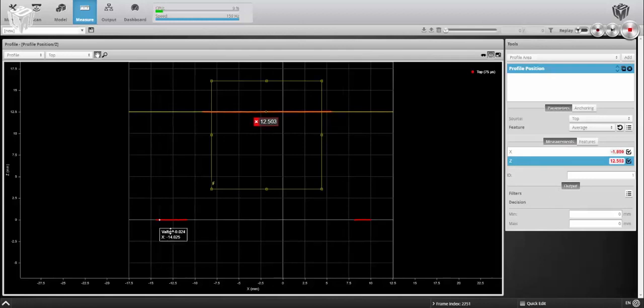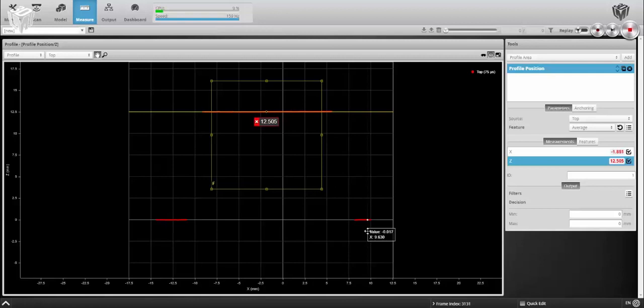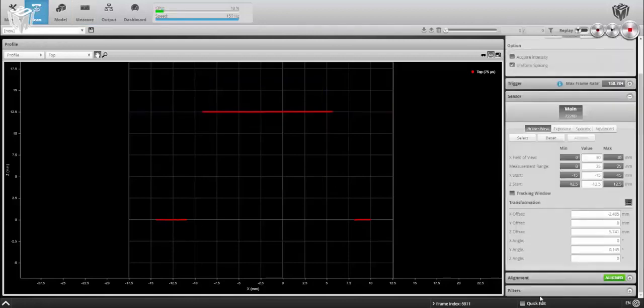You can also see that we've corrected for rotation about y, due to the fact that the table values on the left and right hand side of the connector are relatively the same.